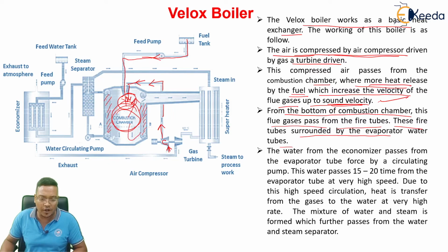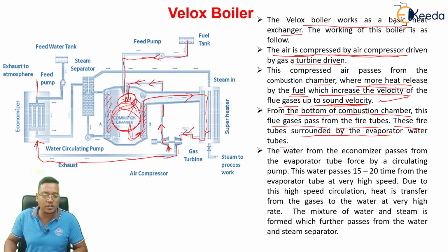From the bottom of the fire tubes, from the bottom of the combustion chamber, the flue gas will go like this, and it will go into the superheater section, like this. After the superheater section, the flue gas will go into the gas turbine, and after the expansion of the flue gas in the gas turbine, the exhaust from the turbine will be sent to the economizer section, where the exhaust will go into the evaporator. This is the flue gas path in the Velox boiler.